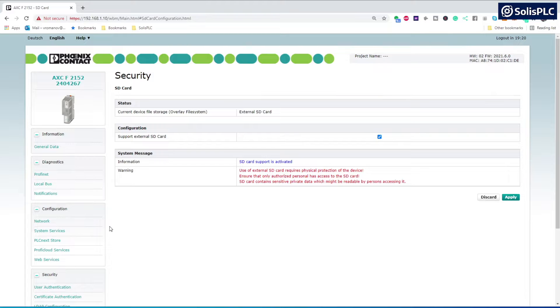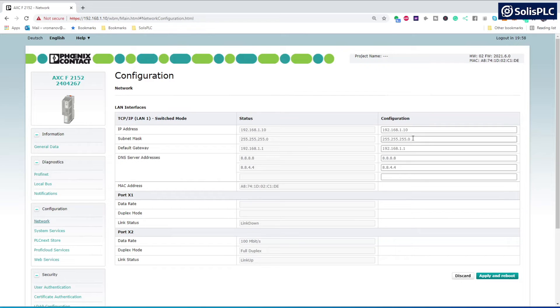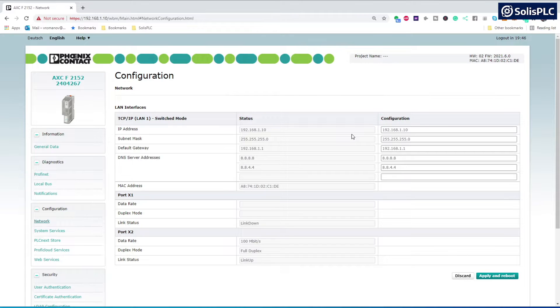The next item we need to take care of is the IP address of our system. If we navigate to the configuration network tab, we'll notice that we still have the default IP address, which is 192.168.1.10. This IP address does not allow the PLCnext to go out on the open network unless there's a router configured to route that specific IP address onto the open web.